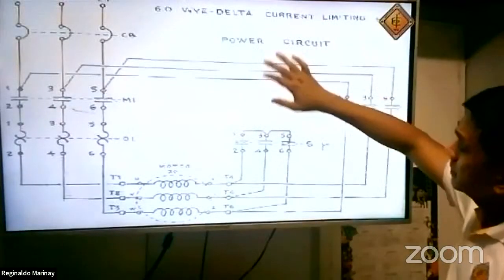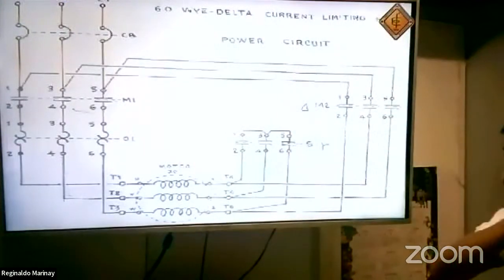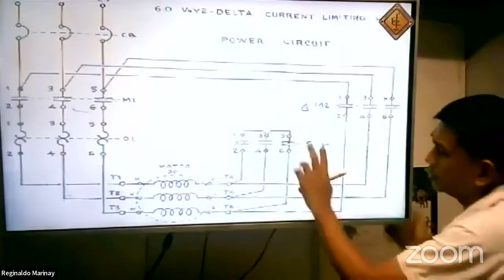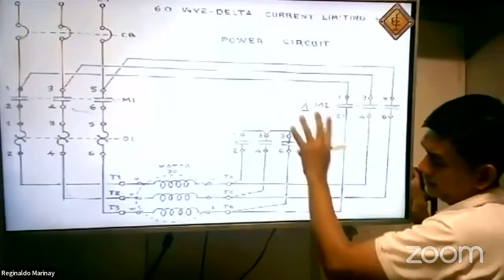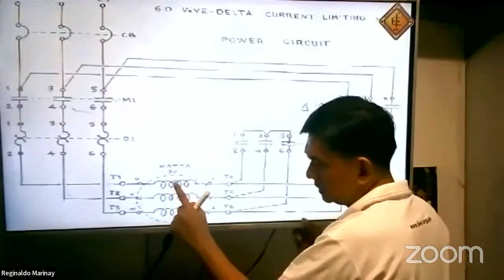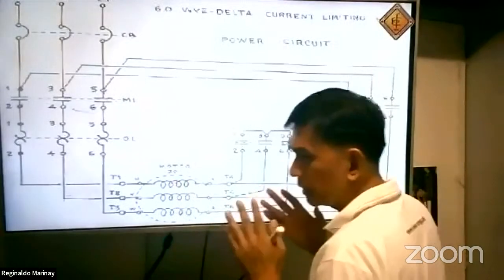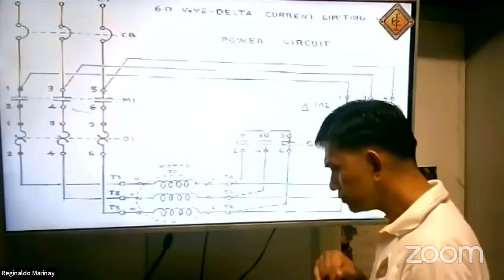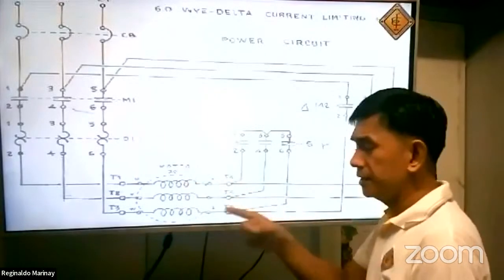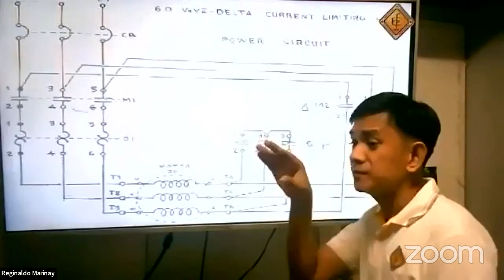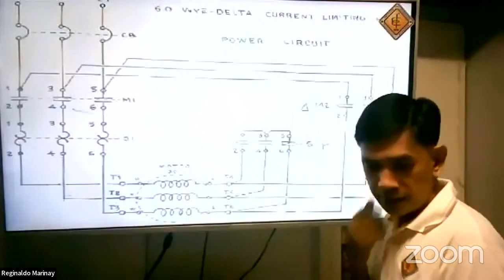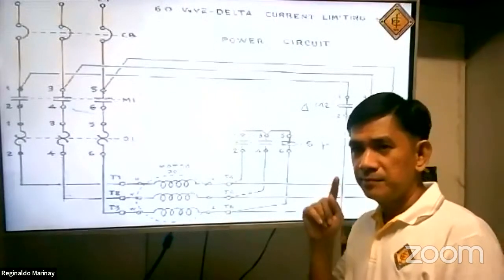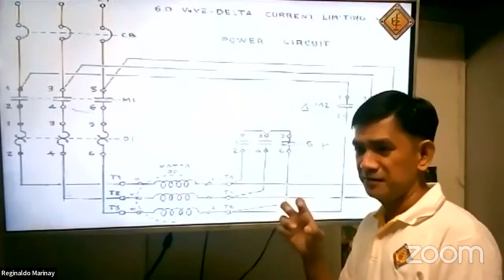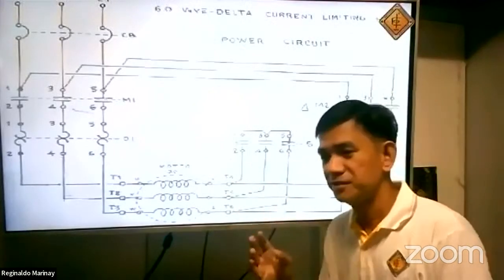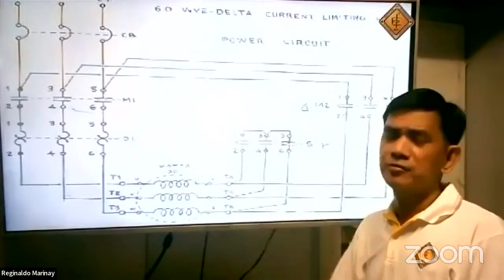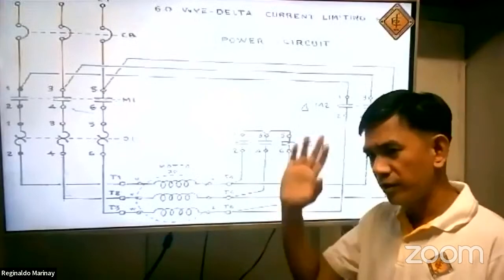We have a Y delta starter. See? This is the power circuit or the motor circuit. This is the Y contactor. This is the delta contactor. This is the winding of this motor. This is a standard motor connection. Next meeting, I will have a live lecture on the 3-phase motor standard connection. I will discuss that next meeting. It's a promise. We're going to study this 6 leads out, 9 leads out, 12 leads out motor. How are we going to connect this?